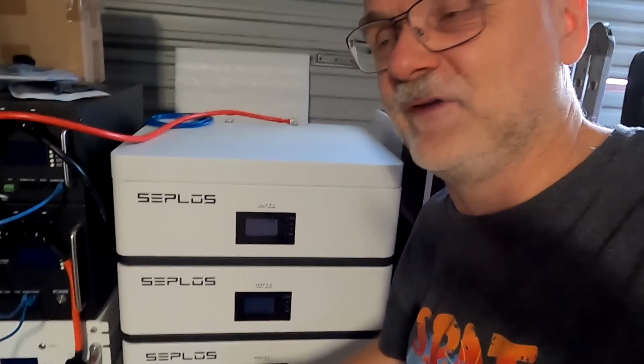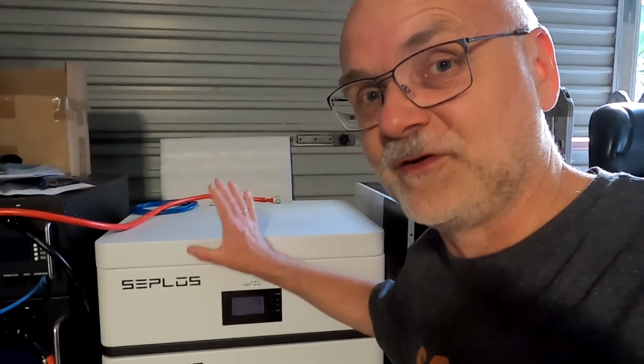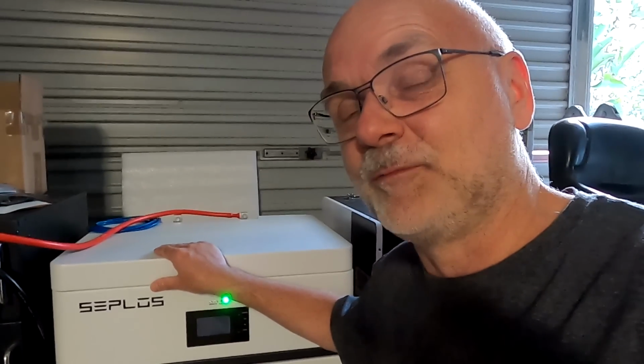I didn't like it. But the major issue with these batteries from Seplos, how they have been delivered, was the severe imbalance of all 3 battery packs they delivered. None of them seem to be actually top balanced. So all the default settings Seplos set in their BMSs did not actually work. The BMSs are cutting out far before that with an overvoltage cell protection. We've seen 250, 280 millivolt of deviation below 55.2 volts, or below 3.4 volts already. That's how much deviation these batteries have.